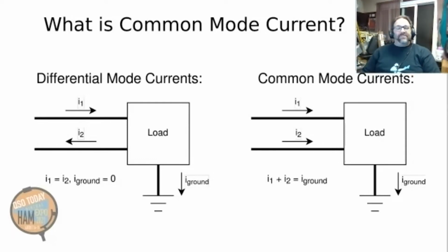But sometimes you have an imbalance between those 2 currents. Let's say I've got 3 amps on the top wire going one direction and 2 amps on this wire going the other direction. I've got 2 amps of differential mode, because 2 amps go this way and 2 amps go that way, but I have an additional amp going this way. So that's 2 amps of differential mode current and 1 amp of common mode current.